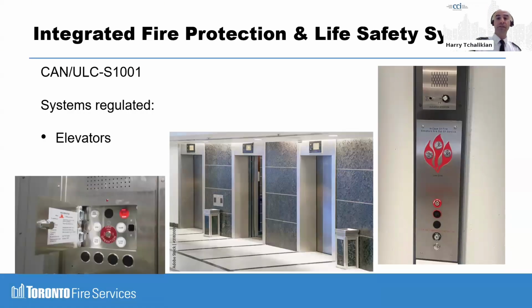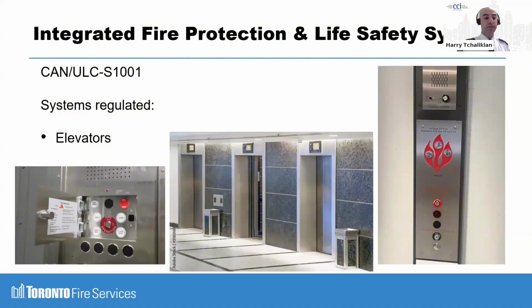Next system is elevators. You're already required to test your elevator functions quarterly as per Part 7 of the fire code. Did it ground? Did all the safety features for firefighters operate? Now with integrated systems, it's a little more detailed. You confirm that it recalled to the primary level. You confirm that it recalled to the secondary level. Initiating device within the elevator hoistway, machine room, control space rooms, elevator recall, and recall indicator illuminates intermittently.